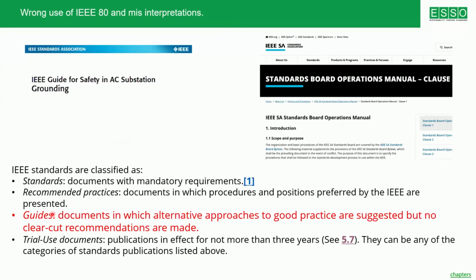For example, if you go to the IEEE website, you can see that IEEE makes standards, which are documents with mandatory requirements. Second is recommended practices. Third is guide. Guide published by IEEE, the definition in the IEEE website is documents in which alternate approaches to good practices are suggested, but no clear-cut recommendations are made. So, IEEE Guide for Safety in AC Substation Grounding is an alternate approach to good practice. That means there is already a good practice existing. And this IEEE 80 is suggesting an alternate approach, but no clear-cut recommendations are made. So please be very careful while making an earthing based on IEEE 80, especially for a hospital.